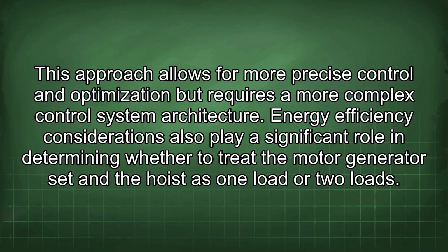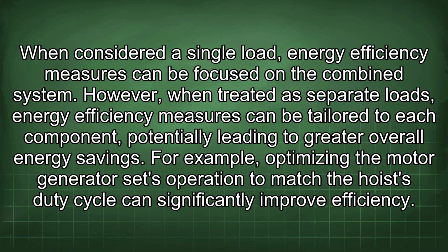Energy efficiency considerations also play a significant role in determining whether to treat the motor generator set and the hoist as one load or two loads. When considered a single load, energy efficiency measures can be focused on the combined system. However, when treated as separate loads, energy efficiency measures can be tailored to each component, potentially leading to greater overall energy savings. For example, optimizing the motor generator set's operation to match the hoist duty cycle can significantly improve efficiency.